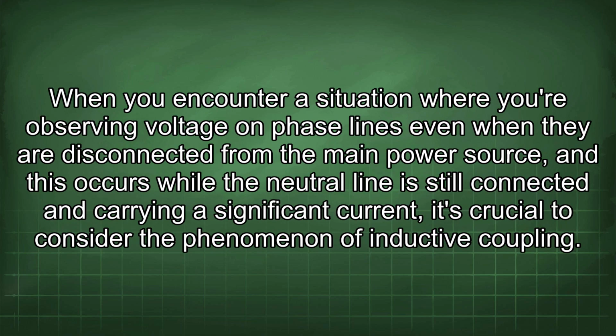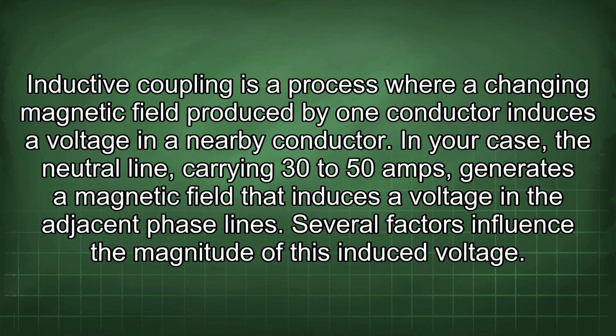When you encounter a situation where you're observing voltage on phase lines even when they are disconnected from the main power source, and this occurs while the neutral line is still connected and carrying a significant current, it's crucial to consider the phenomenon of inductive coupling. Inductive coupling is a process where a changing magnetic field produced by one conductor induces a voltage in a nearby conductor. In your case, the neutral line carrying 30 to 50 amps generates a magnetic field that induces a voltage in the adjacent phase lines.